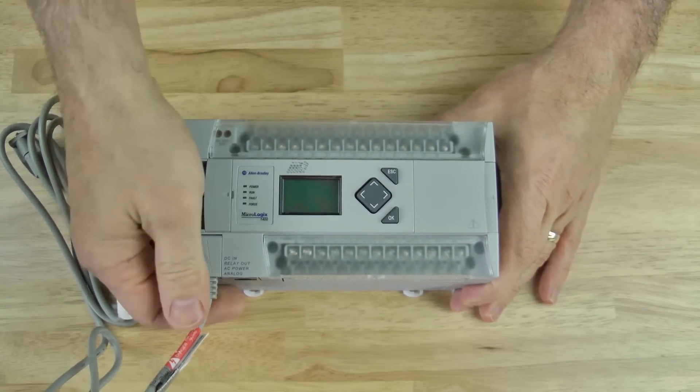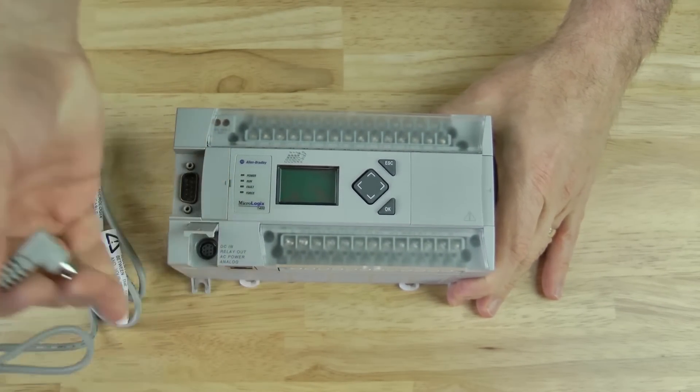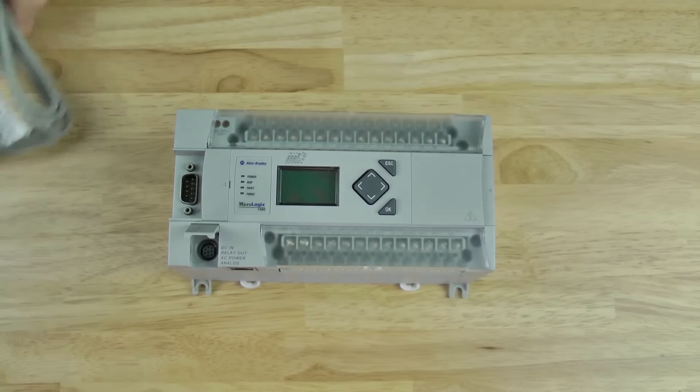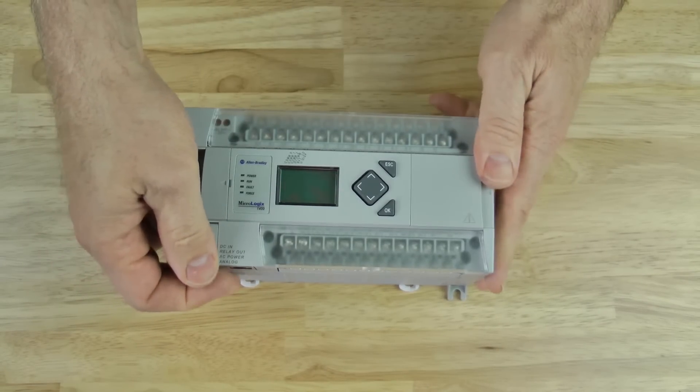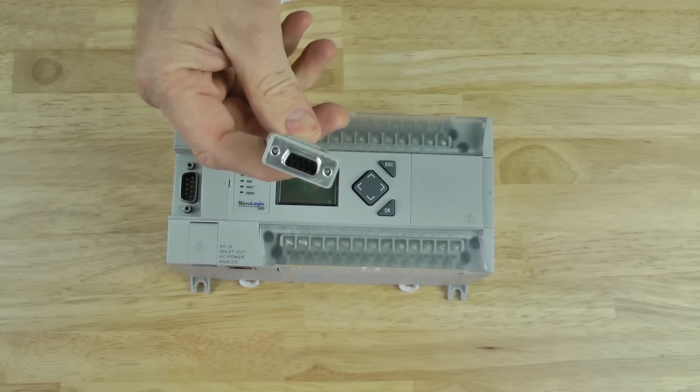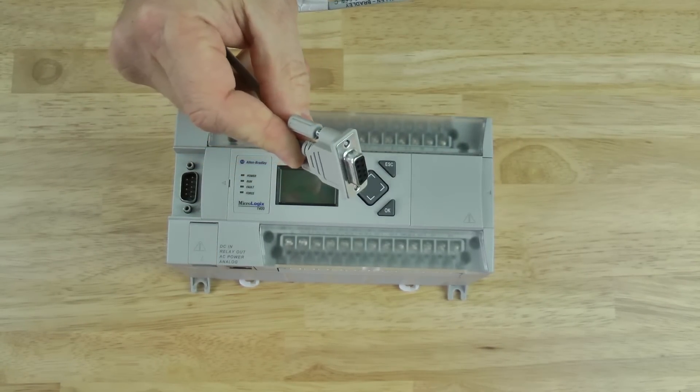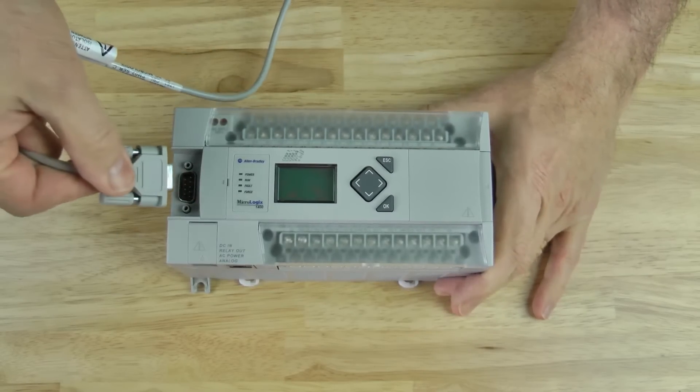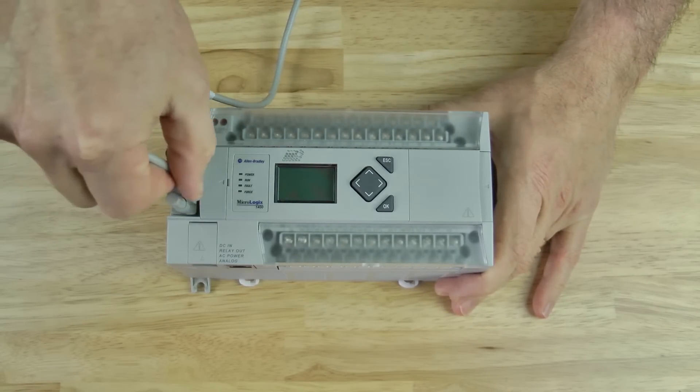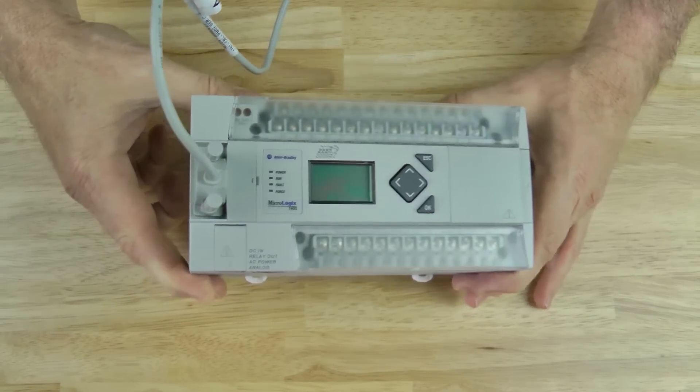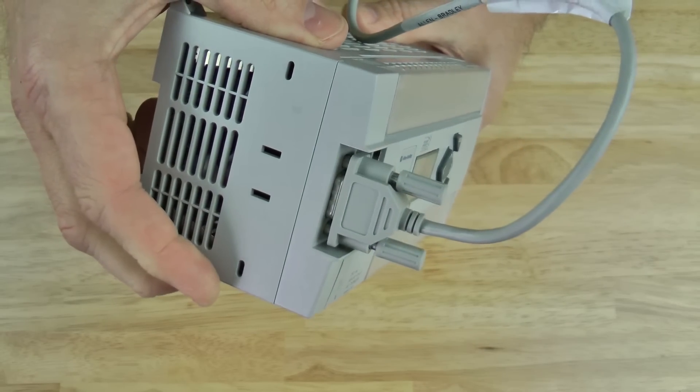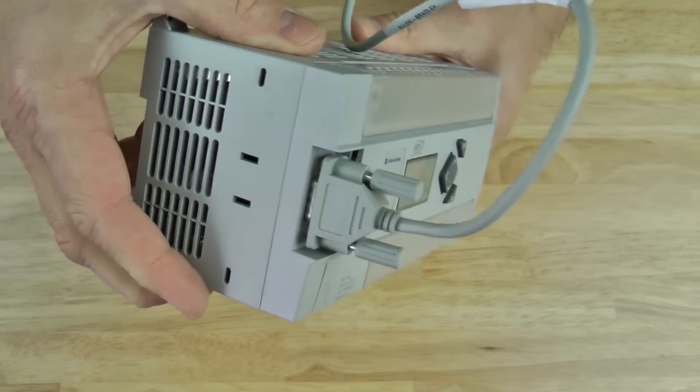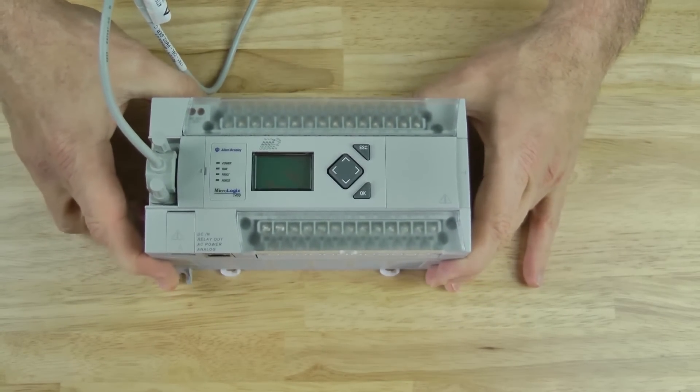Next, let's look at COM2 and a cable with a DB9 connector. To connect this to your computer you'll need a null modem cable or an Allen-Bradley 1747-CP3 cable. It has to have a DB9 female connector, typically at both ends.